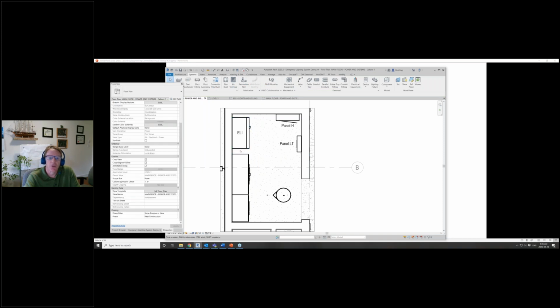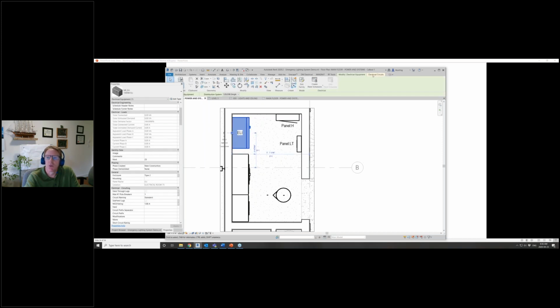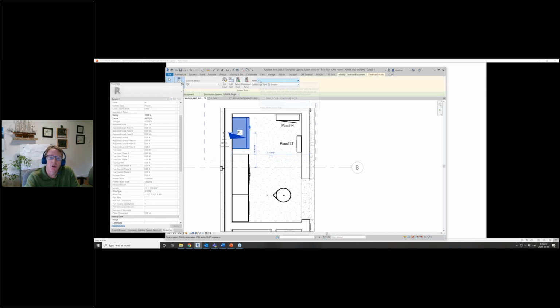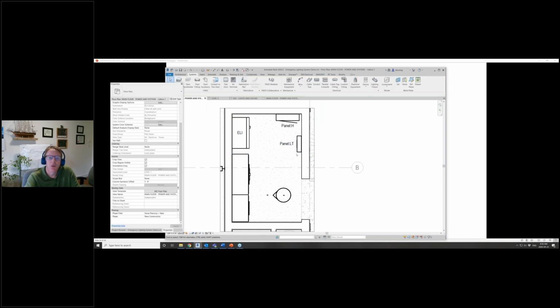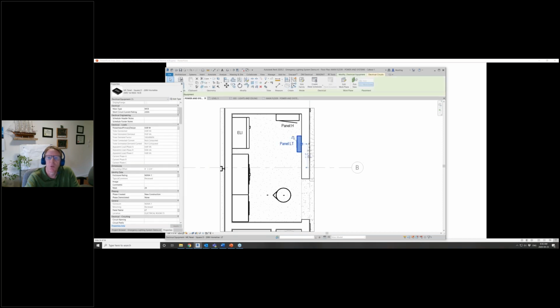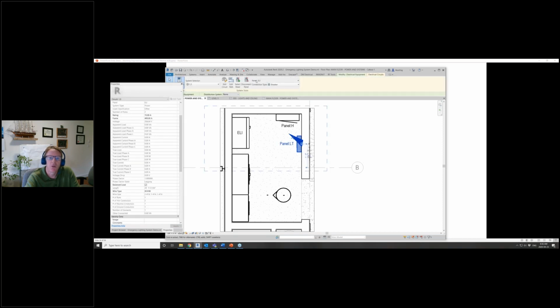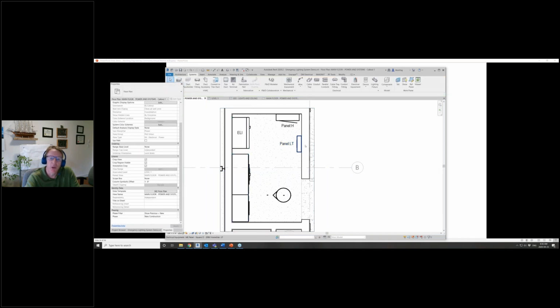So this guy connects - if we see where it's connected, to panel H, our house panel, which is here. So panel H, our house panel, connects to the emergency lighting inverter. And in this case, I have another panel, which we call panel LT for lighting. This panel is connected to the ELI. So H drives the ELI, drives this little panel LT. And this panel LT can be used to drive lighting all over your building.